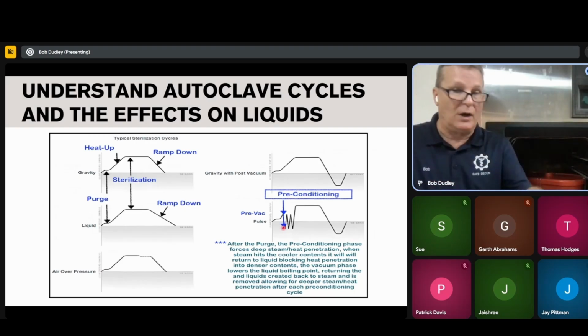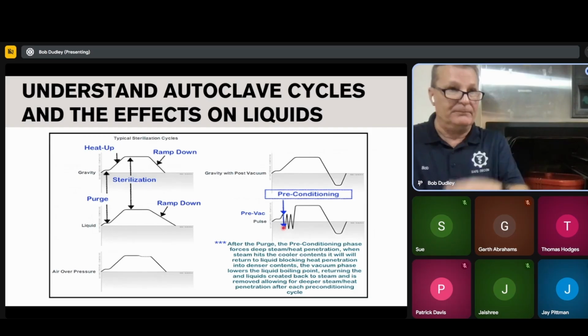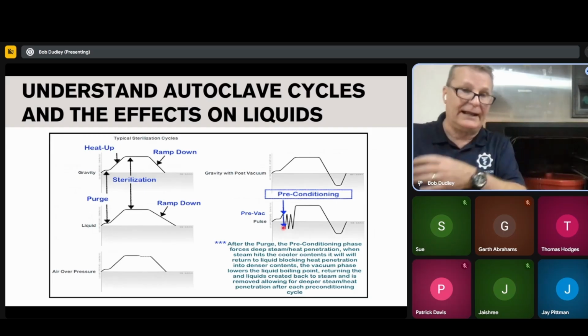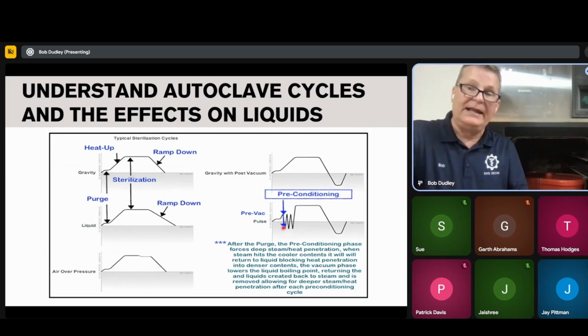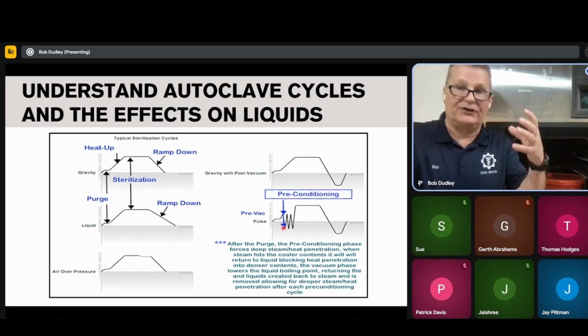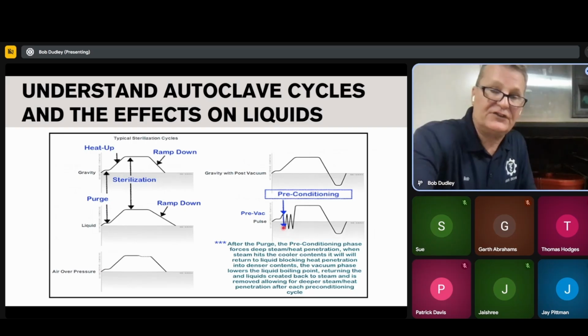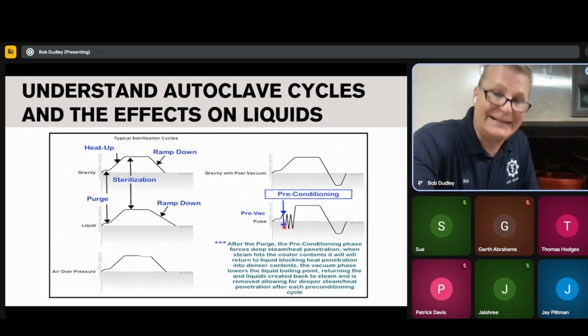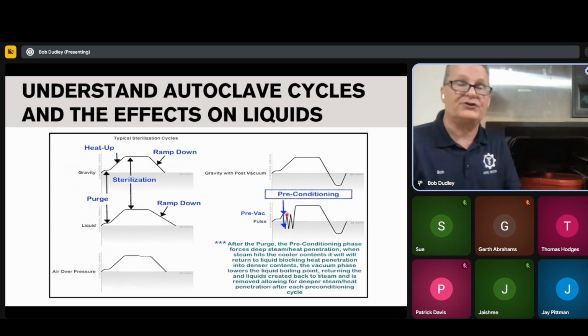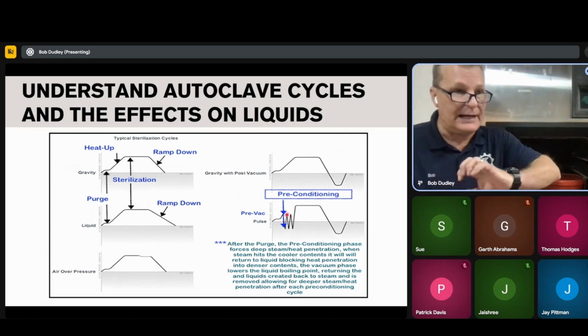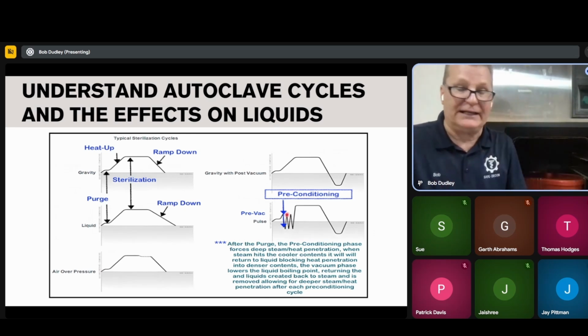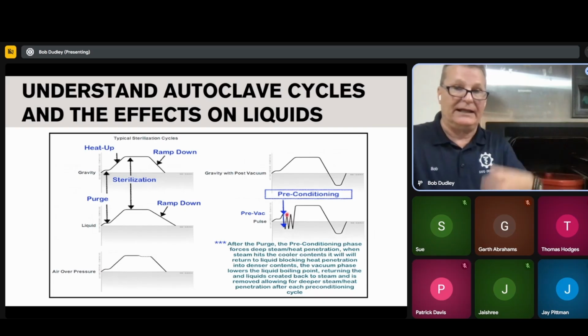You have cool water coming through, and the mist will attack the cool water, and it all goes down the drain. And the inside of the chamber is now conditioned to accept pure steam gas, no mist. It just pulled whatever it is. So now you get that hard, violent push back of pressure in. Now it can drive, it jackhammers it in deeper into that load.